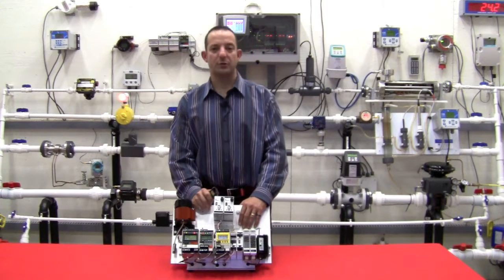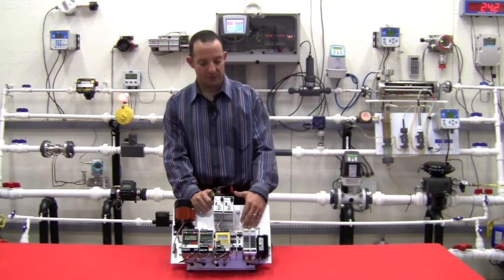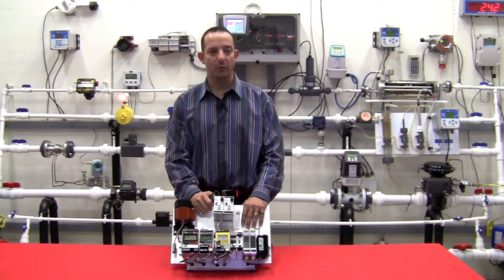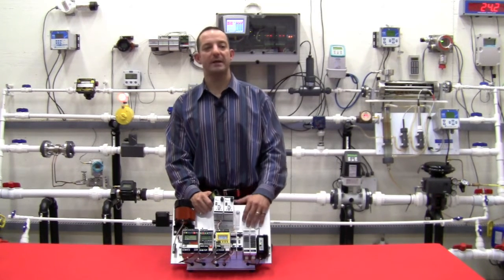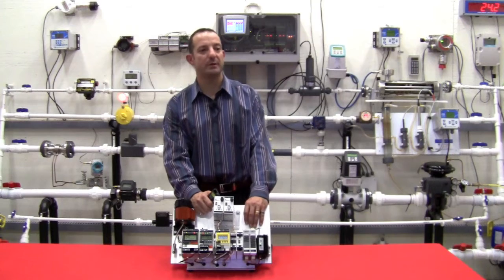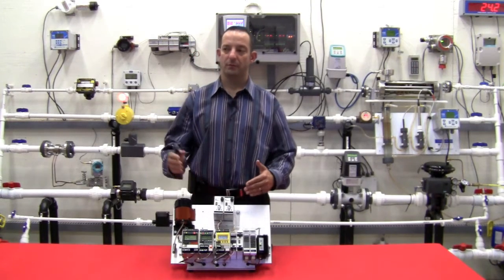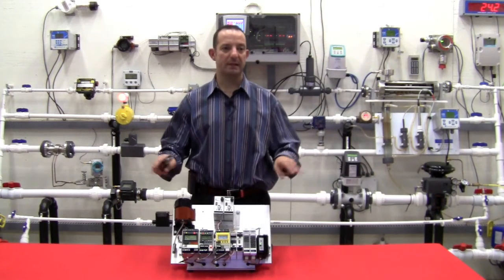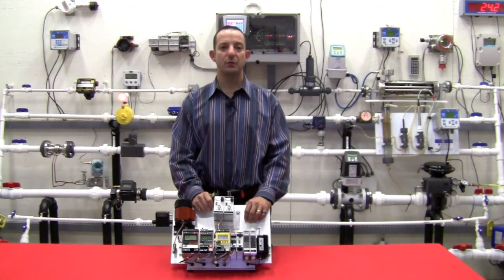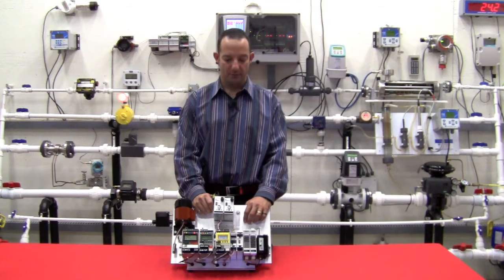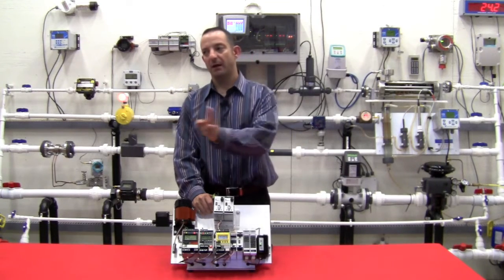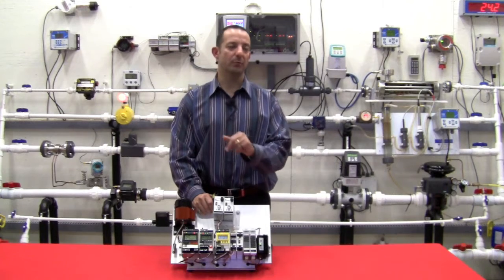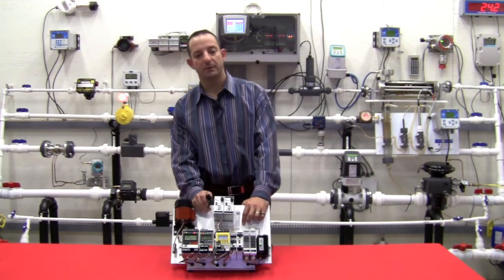Another reason to use a temperature transmitter is that analog signals are easier to share with multiple receiving devices. Back to my example of a temperature transmitter being used for both a measurement system and a control system. If you're going to split that signal, it's easier to do with an analog signal splitter rather than trying to share the thermocouple millivoltage or the RTD signal between those two systems.